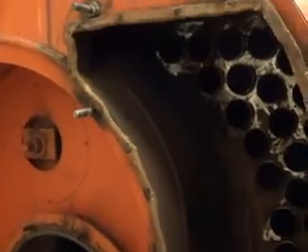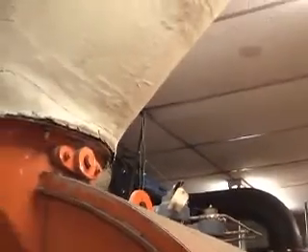Now remember, this has got the flame coming down the pipe — it's not the water — but you still have the potential for a water leak. It starts off in this big round tube in the middle here. This is the blower — it's blowing air — and then you're getting your gas in there. That's the Morrison tube that goes down, probably comes back, and then there's a break right here and it hits this wall, then probably goes back through the upper wall and out the stack. There's your stack right there, and that steel pipe is your steam — so all this is exhaust.